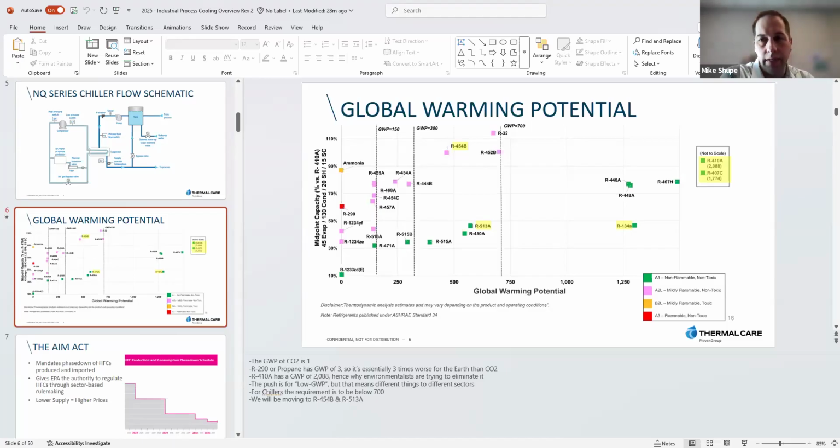And they made a rating system based on CO2. Carbon dioxide also traps solar radiation, but it has a GWP rating of 1. And then if you look at that red dot in the middle there to the left of R290, R290 is propane. Propane has a GWP rating of 3. So propane traps 3 times the amount of solar energy that CO2 would.